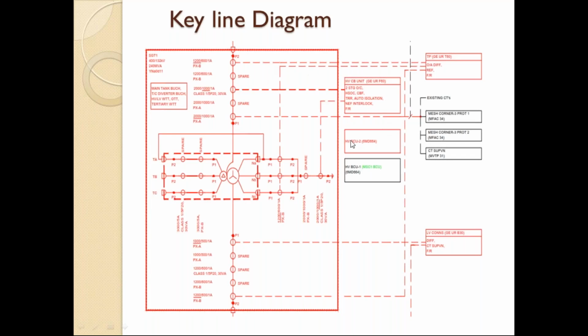We can show this elaborate detail in the KLD. By seeing this KLD, an engineer can understand the type of protection — here in the CT we have connected the overall transformer protection. This CT is connected as a CB unit, and it's also connected for the bus bar protection.